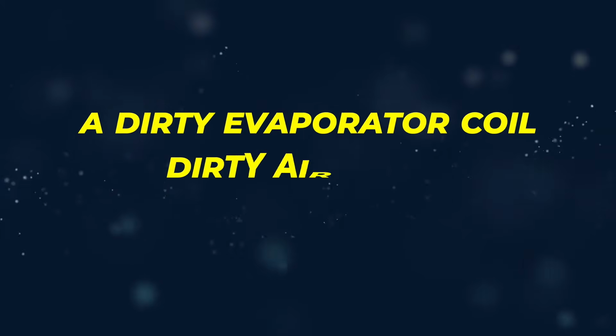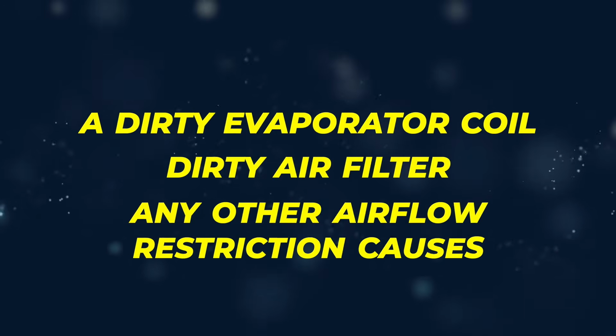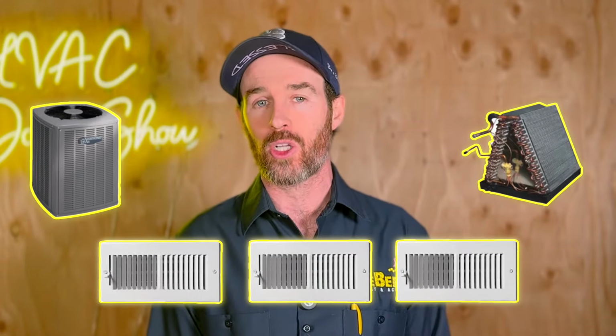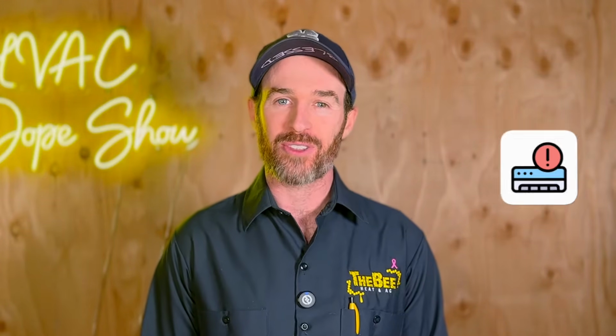But the reason that a dirty condenser will cause the same issues that a dirty evaporator coil or dirty air filter or any other airflow restriction causes is because it does not allow for proper heat transfer from the refrigerant at the condenser. So the combination of a dirty condenser in conjunction with a dirty evaporator coil and/or too many registers being closed and/or a dirty filter at the same time, these are all things that are going to add up to basically a recipe for disaster for your system. It doesn't stand a chance to run without icing.